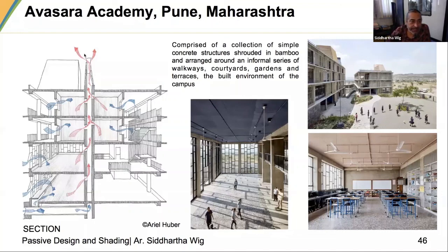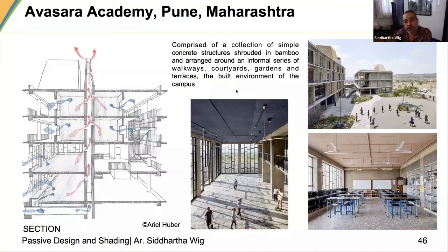There is an air inlet at sill level on the ground floor with cool air coming in. Hot air rises through the chimney, and on the roof there is a solar chimney top — glazed, black inside — which heats the air and forces ventilation upward. The roof shapes are interesting and a lot of waste tiles and waste stone were used in the flooring.